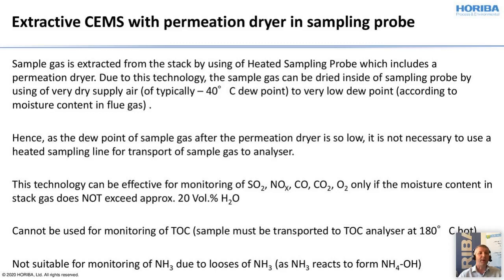The next one is the permeation dryer in the sampling probe. When we have a permeation dryer directly in the sampling probe, we can avoid having the heated line. I mentioned before it might be up to a 100 meter heated sample line, and this of course takes a lot of energy. So what we are doing is that we put the dryer, which is normally installed in the cabinet, already at the sampling probe, and we don't need a heated sample line bringing the gas from the probe to the analyzer cabinet. The technology can be used effectively for the same components as before, but only up to a moisture content of up to 20 volume percent humidity.